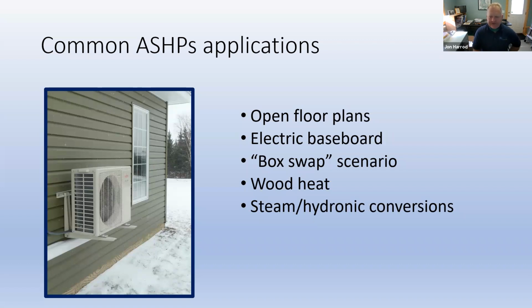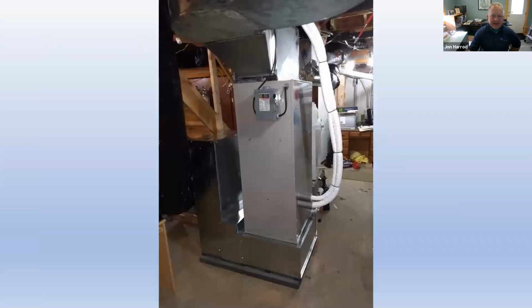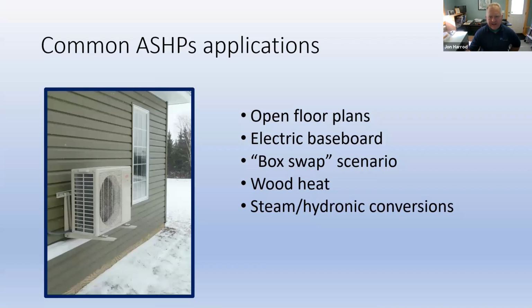Another application that I think will really allow us to scale this is what I call the box swap scenario. It's usually not a simple box swap, but you're taking a cold climate heat pump and installing it in place of the old furnace, taking advantage of the existing ductwork to get conditioned air to all the rooms. In almost every case, we do need some modification of the ductwork, invariably increasing the size of the supply ducts to increase airflow, and often adding additional supply runs to make sure we get adequate airflow through the system.